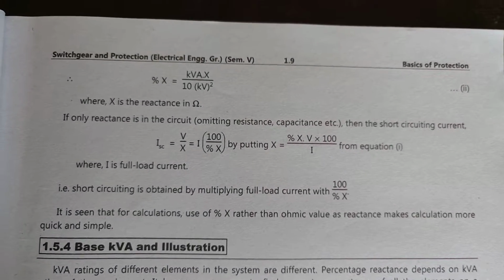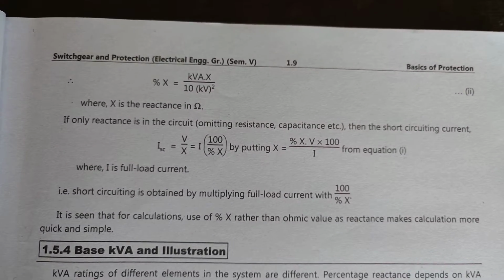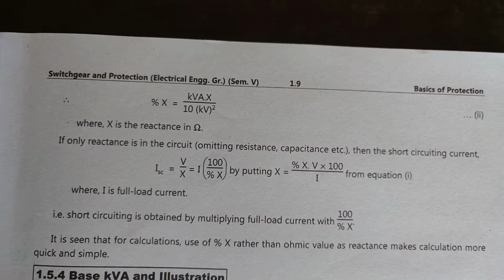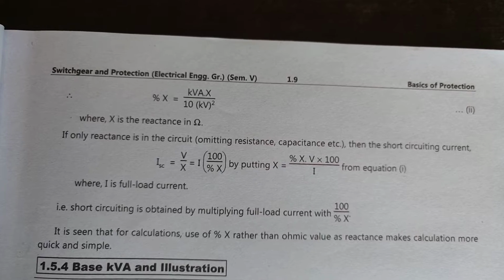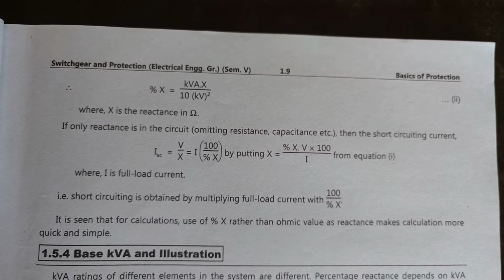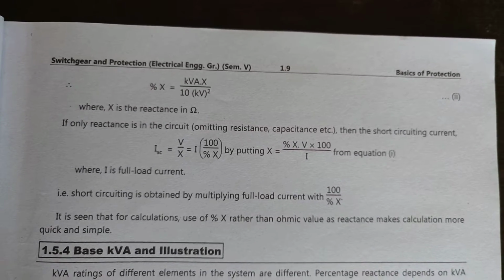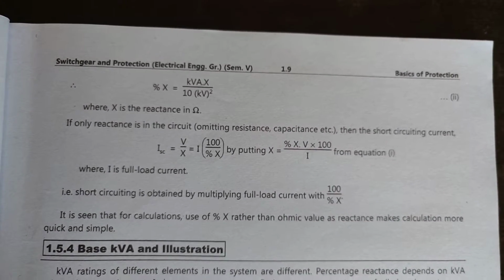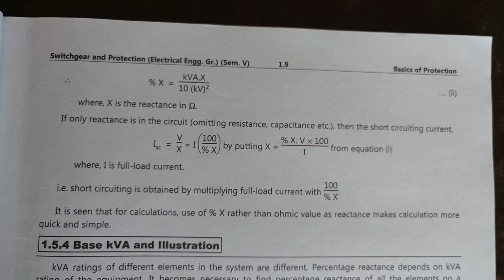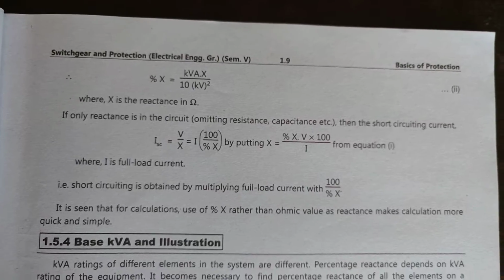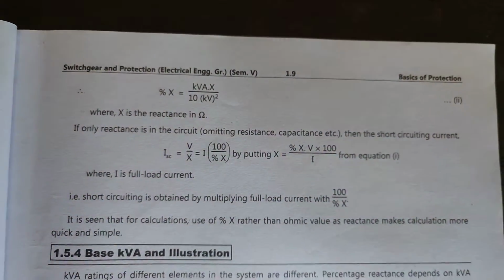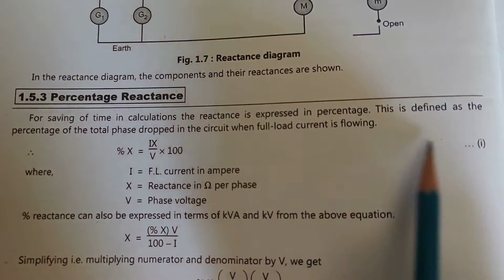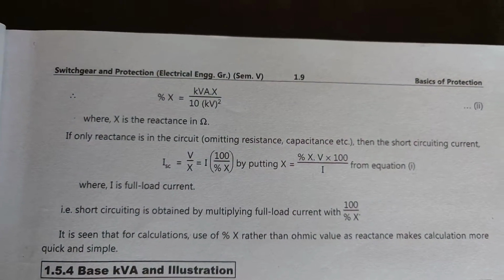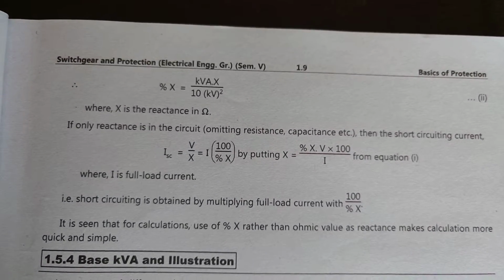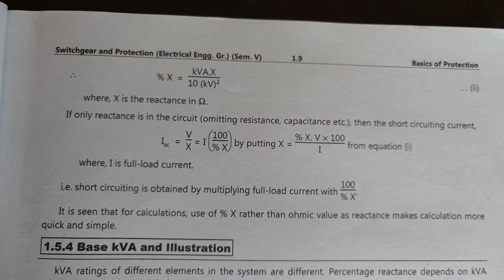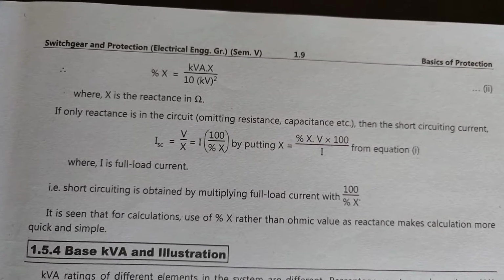If only reactance is in the circuit, that is omitting resistance, capacitance, etc., then the short circuit current is given by ISC equals V upon X, that is I into 100 upon percent X, where we put X equals percent X into V into 100 divided by I. This is from equation number 1. From this equation, where I is full load current, the short circuit current is obtained by multiplying full load current with 100 upon percent X.